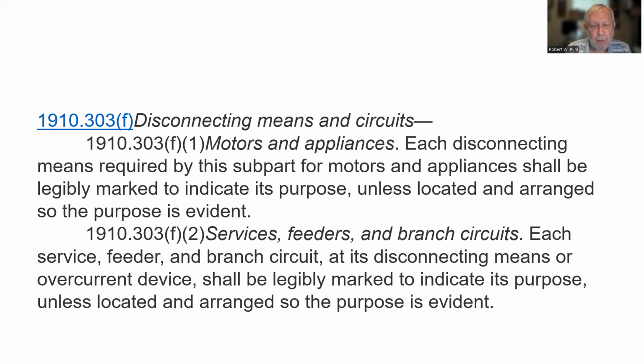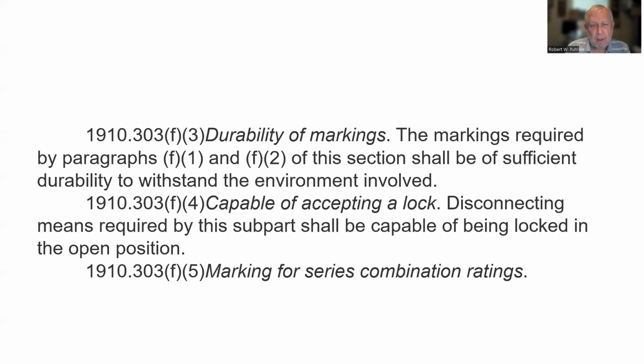Each service, feeder, and branch circuit at its disconnecting means or overcurrent device shall be legibly marked to indicate its purpose, unless located and arranged so that the purpose is evident. Durability of markings, same as before, capable of standing the environment, capable of accepting a lock. Disconnecting means required by this subpart shall be capable of being locked in the open position. I wonder what that's for. Maybe lockout.